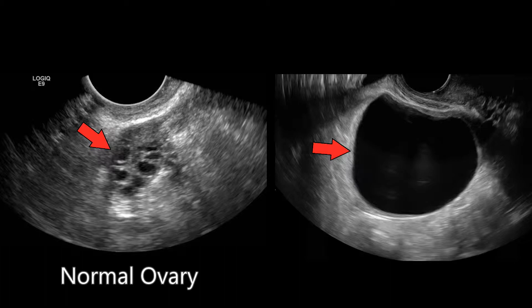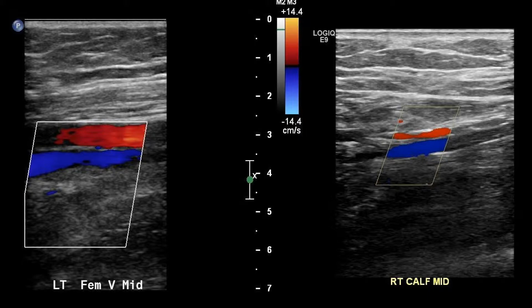Ultrasound is also great for evaluating blood vessels in the body using a technique called Doppler ultrasound. You know how when a train is coming toward you with its horn blowing, the pitch of the horn changes as it passes you? That's called the Doppler effect, and it occurs because the perceived frequency of the sound coming from the horn changes as it's coming towards you, passes you, and moves away. Well, if you replace the listener with the ultrasound probe, the train with the blood in a vessel moving toward or away from the probe, and the horn with the ultrasound signal reflecting back from the moving blood, we can do some math with angles and such to figure out both the direction and speed of the blood flowing within the vessel. When the ultrasound machine is set to color Doppler mode, the vessels turn from black to red and or blue depending on if the blood is flowing toward the probe or away from it.